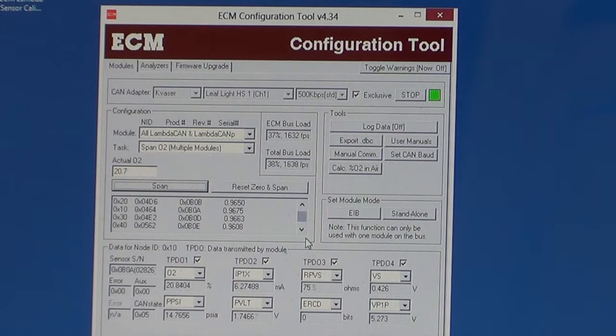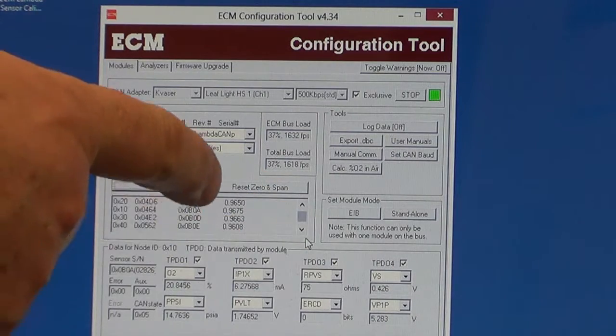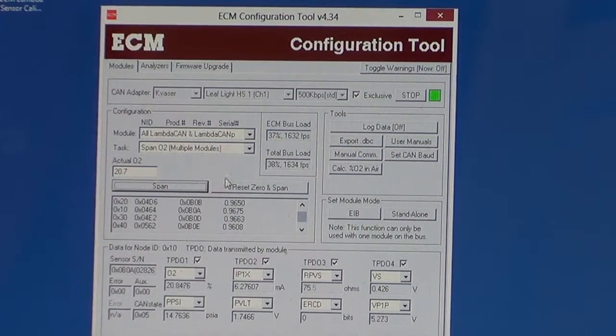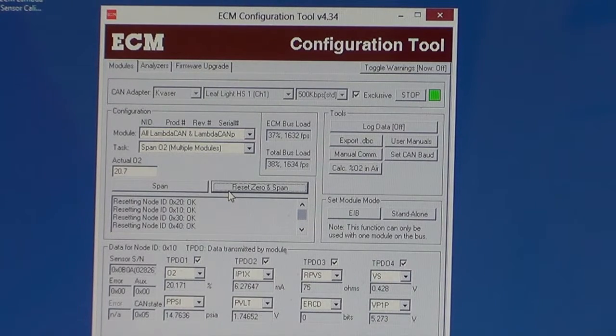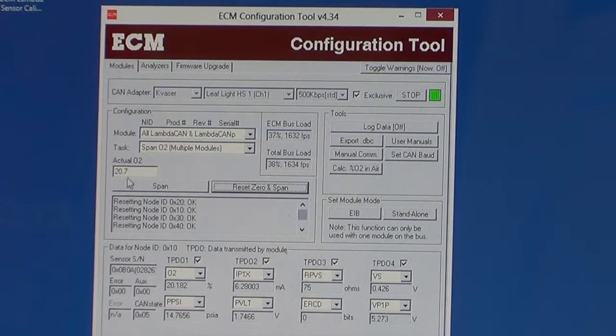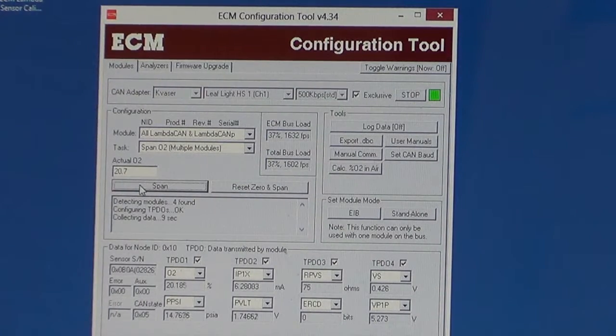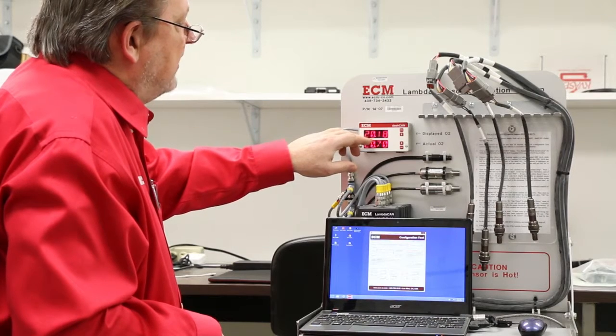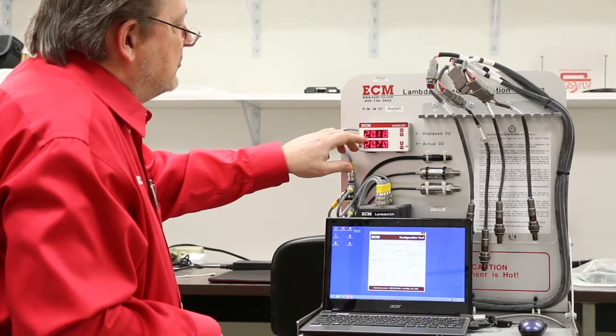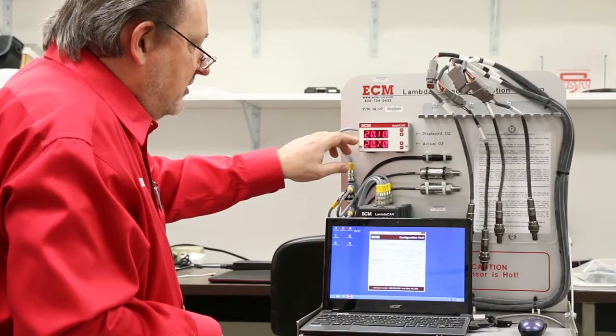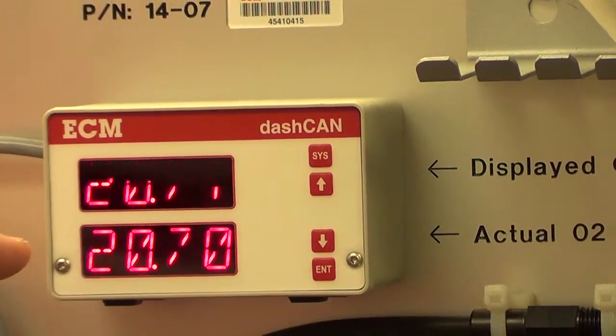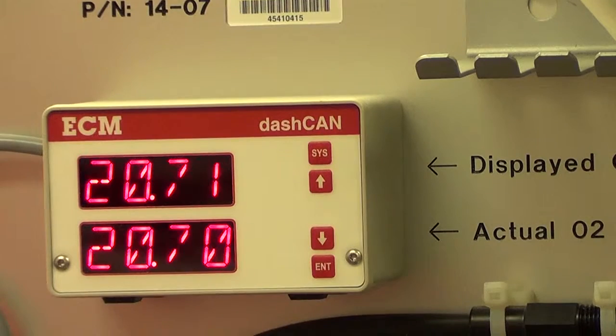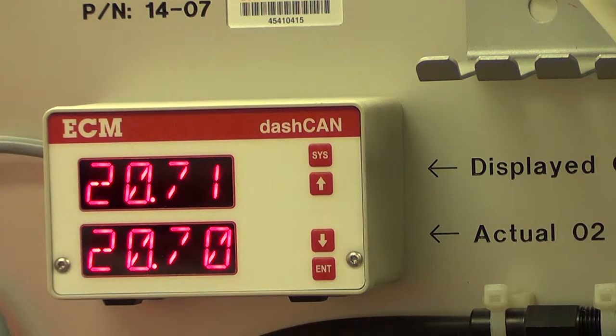Now if you make a mistake while you're doing this, just reset the 0 and span again. Click. Hopefully you'll get everything's okay. And then you don't have to wait an hour if it's already been sitting. Do your span again. When we punch 20.7 and span, you'll see the first sensor before the span is showing 20.18, so it's slightly aged. It's 4, 3, 2, 1. Okay, the calibrations are done. Click. It's going to go up to very close to the target 20.7.